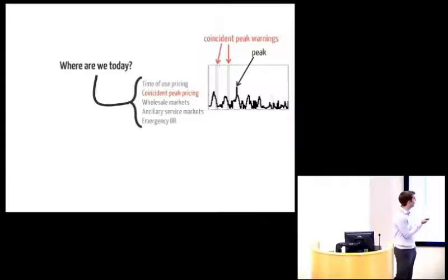For example, in Fort Collins, Colorado, HP has a data center that is forced to participate in this. About half of their energy budget, their monthly bill, which is $2 to $4 million a month, goes to paying these coincident peak penalties, basically. So these are a big deal in terms of their bill, but they're really terrible in terms of risk for the data centers. So no data center would choose to do this.